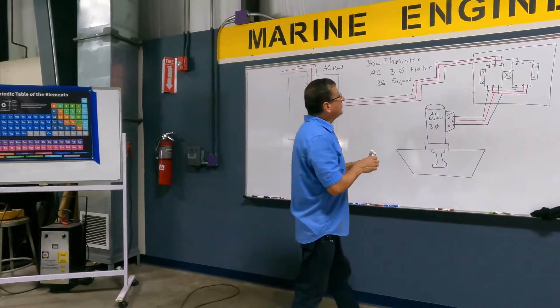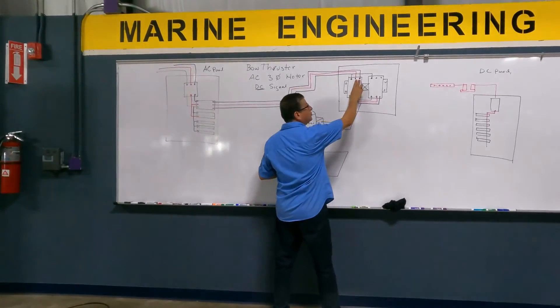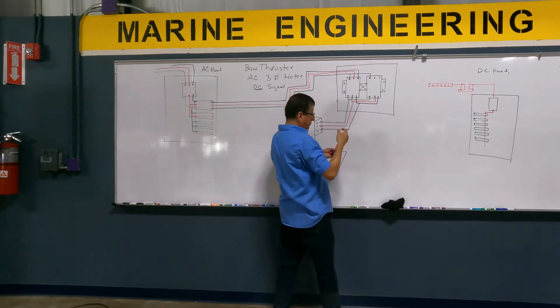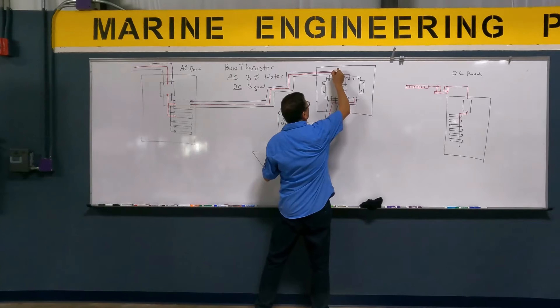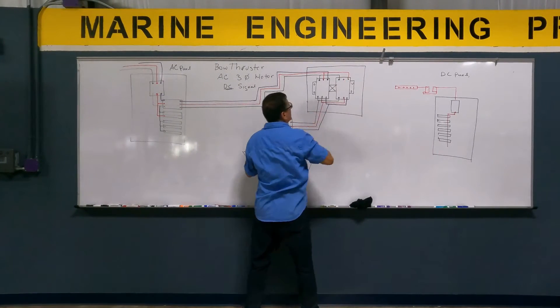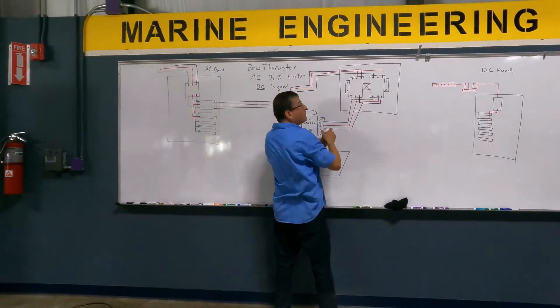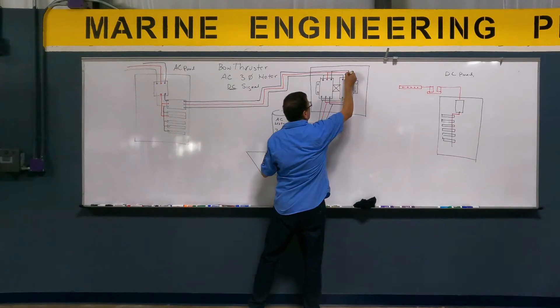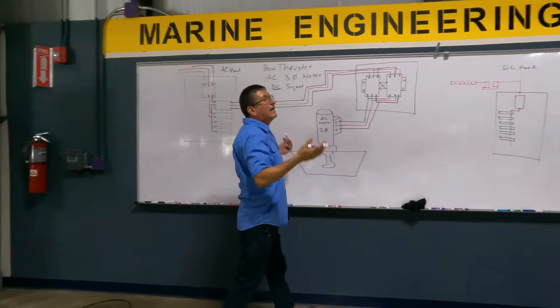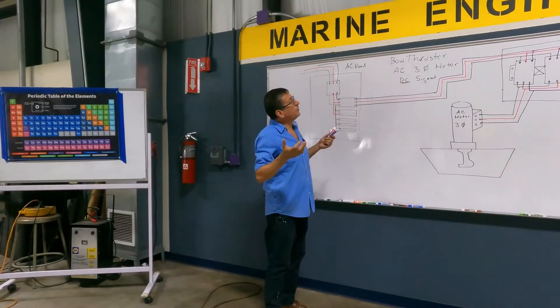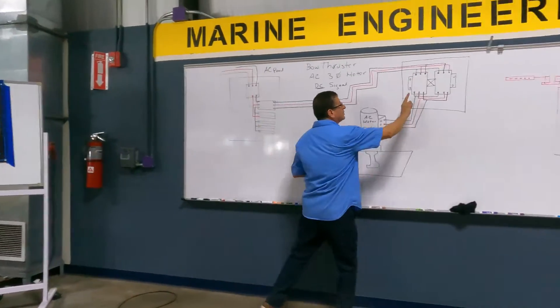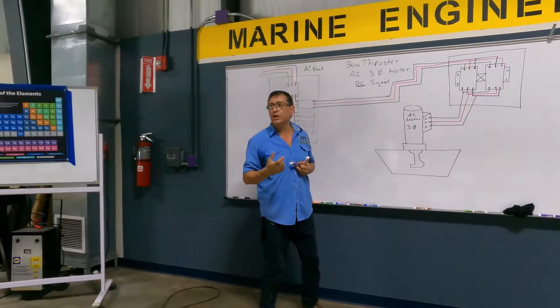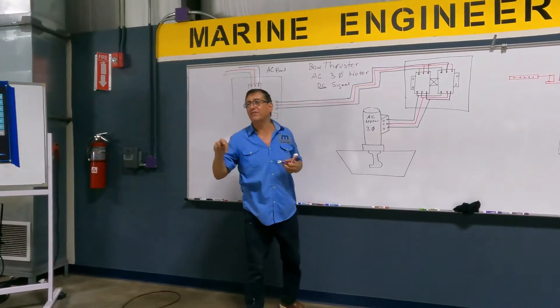Now here is the secret: I am going to switch those two phases in this contactor. The red phase is in the second slot — in this contactor it will be in the third slot. The purple phase is in the third slot — in the other contactor it should be in the second slot. That is the procedure to reverse the rotation of this AC three-phase motor when the bow thruster uses a three-phase reversible motor.